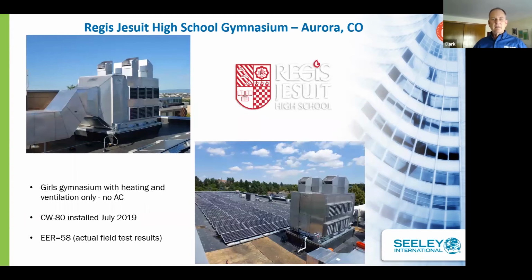So if we look at some applications, here's a good one we did in Denver. This is at Regis Jesuit High School, the girls' gym in Aurora. Previously, they had no air conditioning for the gym. All they had is a heating and ventilation unit. They put in a CW80 unit. It was installed in July of 2019. Here's a picture on the right. You can see it on the roof. So this is providing conditioned air. I tested this unit in the field shortly after it started up and calculated an EER of 58.